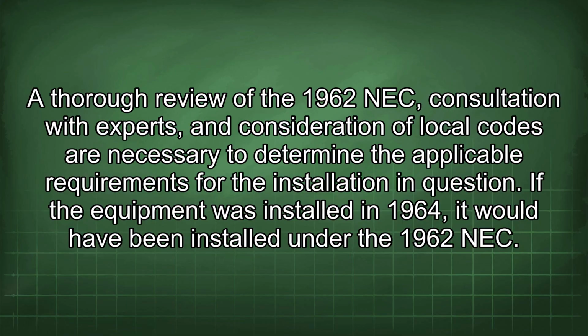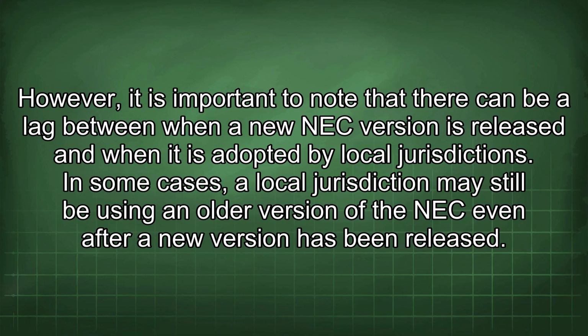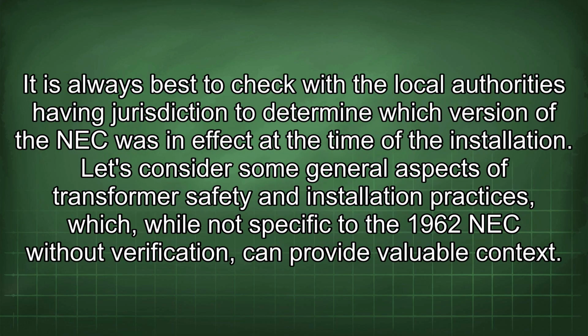If the equipment was installed in 1964, it would have been installed under the 1962 NEC. However, it is important to note that there can be a lag between when a new NEC version is released and when it is adopted by local jurisdictions. In some cases, a local jurisdiction may still be using an older version of the NEC even after a new version has been released. It is always best to check with the local authorities having jurisdiction to determine which version of the NEC was in effect at the time of the installation.